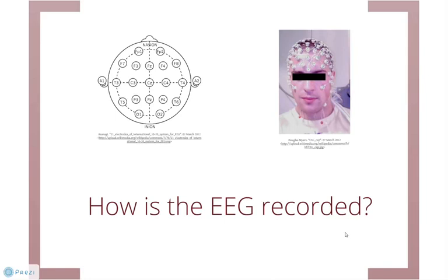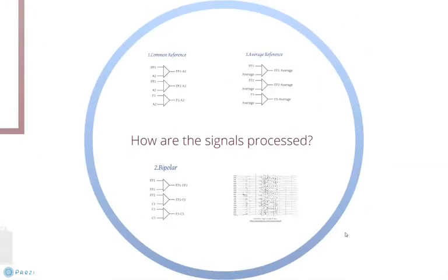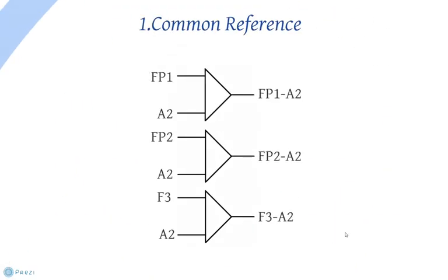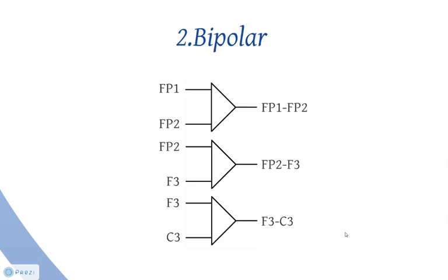So now we've got all the electrodes in place, we need to start collecting signals. The problem is, what do we compare them to? The most obvious way would be to use an arbitrary common reference. The electrode signal is fed into a differential amplifier with a reference electrode common to each EEG signal. This technique is useful in that it should reveal the true nature and amplitude of the signal. However, in reality, the reference is often active, and the distance between the electrodes can allow interference to obscure the signal.